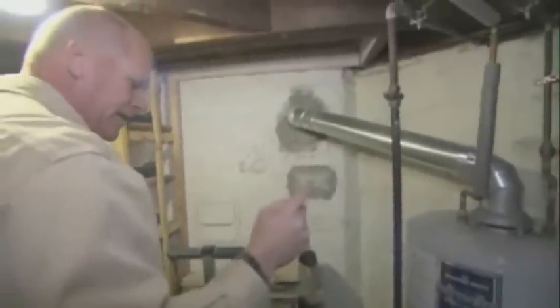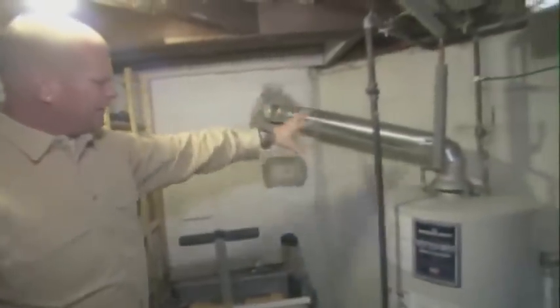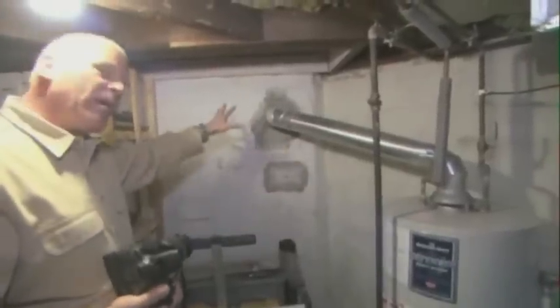And at this point right now, I am concerned about this, and I'll tell you why. I know there's a fireplace upstairs. The hot water heater is now going through the chimney. Is this correct? Is everything fine here? It's a great question in my mind and needs to be addressed. Do we have any issues with this gas heater running into the chimney? Do we have a possible issue of off-gassing coming back in the house? It's a question. It should be checked.